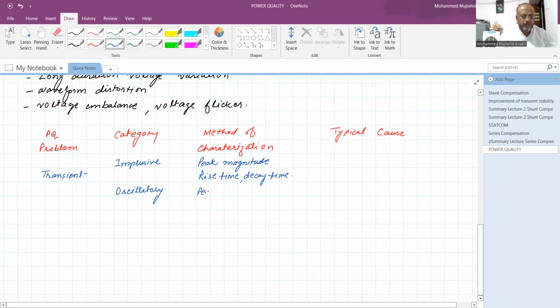And second is the oscillatory transient. It is characterized by peak magnitude of the oscillatory transient as well as frequency components. How many frequency components are there? So these two parts are for the impulsive transient, and these two parts are for the oscillatory transient. What are the typical causes? Definitely for the impulsive one, it is a step change. So lightning stroke is a natural phenomenon, and another is transformer energization.